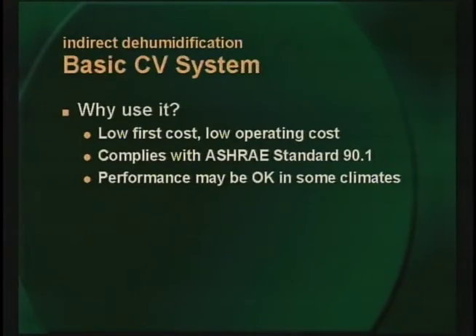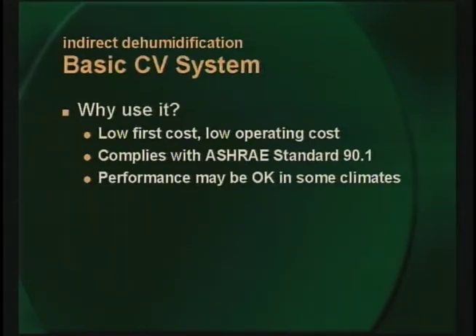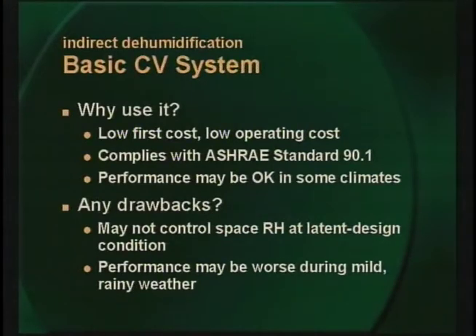With no mechanical or control devices to enhance its ability to dehumidify the space, this system provides indirect dehumidification control, since coil latent capacity is really independent of space latent load. This basic air handling system controls space relative humidity to about 52% at sensible design, but allows it to rise to nearly 67% at latent design. Many designers use this basic constant volume system because it has low first cost and low operating cost and complies with ASHRAE Standard 90.1, resulting in acceptable space conditions at sensible design in any climate. However, space relative humidity can rise to unacceptable levels at part load. At other outdoor conditions the results might actually be even worse. When it's 72 degrees and raining, lower sensible loads would result in higher supply air temperature and raise space relative humidity even further. When space relative humidity rises above 60%, the system no longer meets the recommendation of ASHRAE Standard 62.